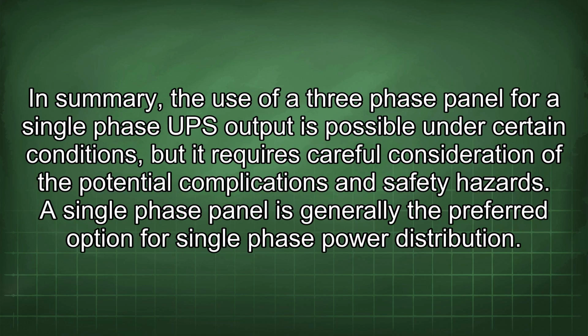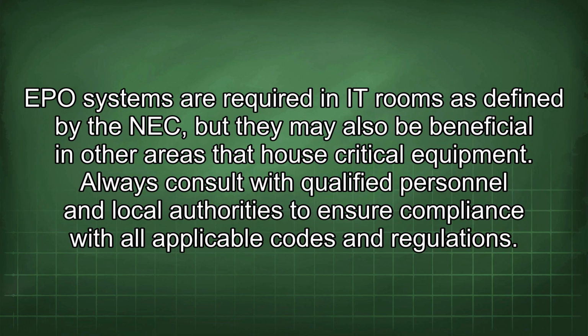In summary, the use of a three-phase panel for a single-phase UPS output is possible under certain conditions, but it requires careful consideration of the potential complications and safety hazards. A single-phase panel is generally the preferred option for single-phase power distribution. EPO systems are required in IT rooms as defined by the NEC, but they may also be beneficial in other areas that house critical equipment.